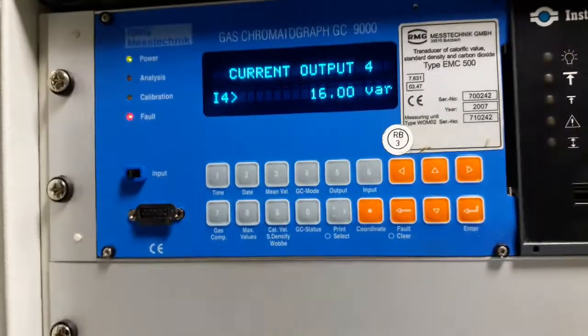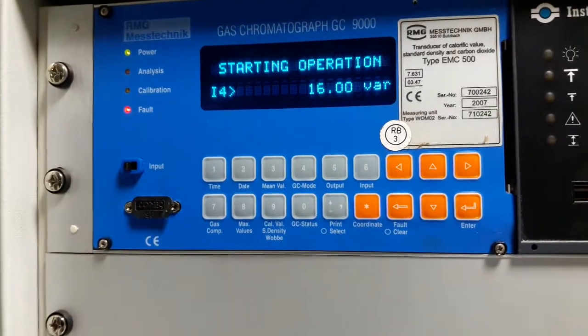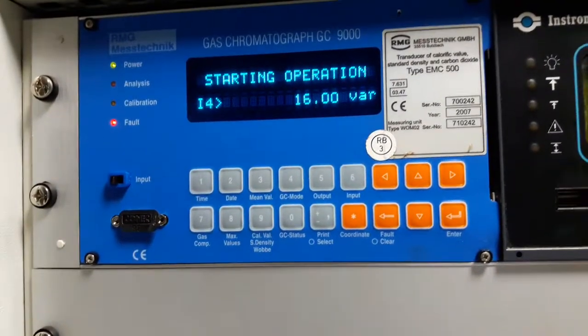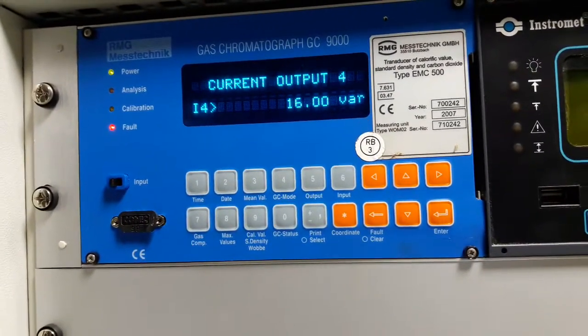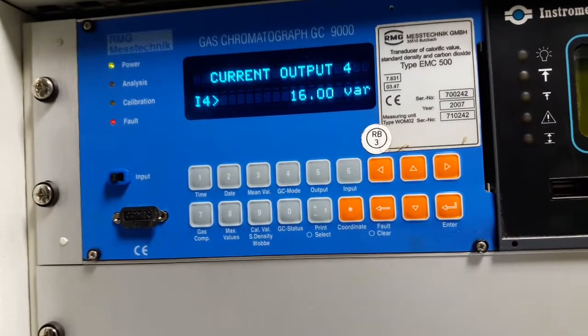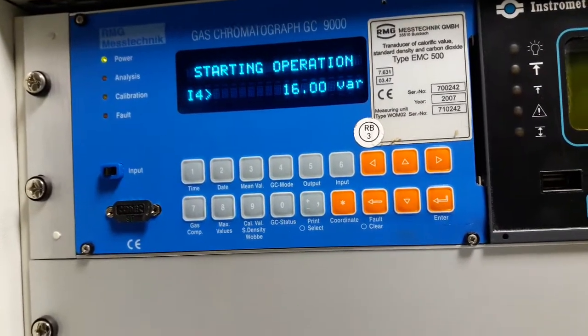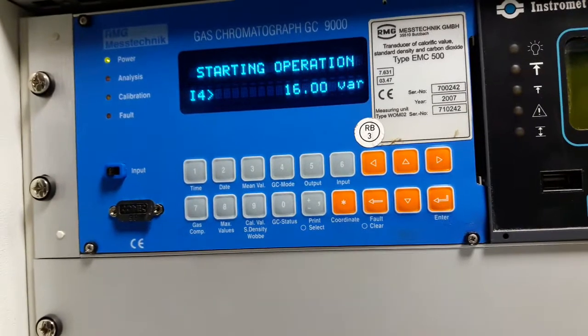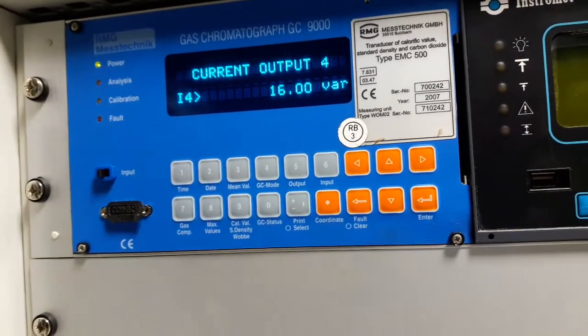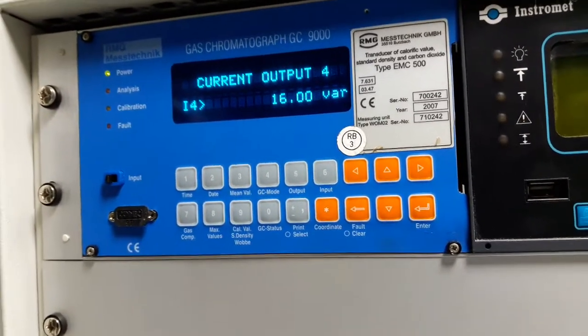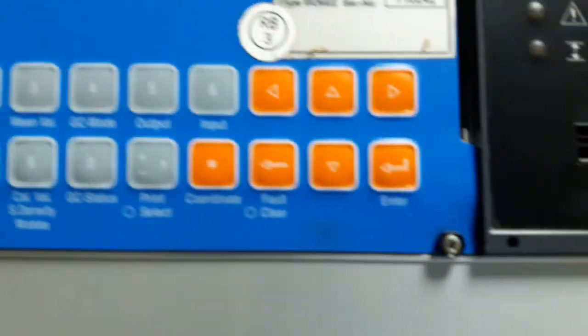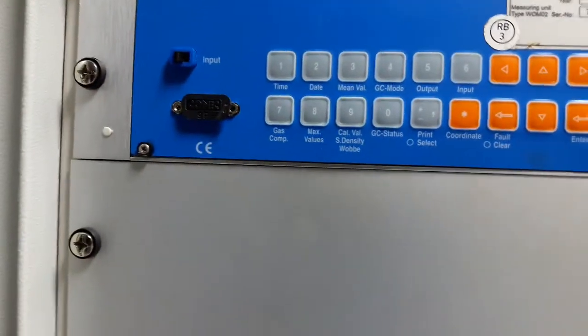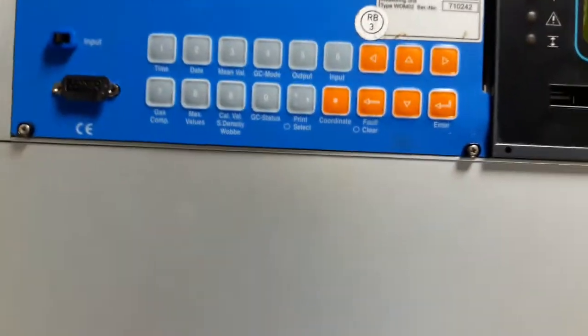This gas chromatograph GC 9000 model, we set it to measure superior calorific value, Wobbe index, and inferior calorific value, standard density, relative density, temperature at base condition, and temperature at condition of superior calorific value. So before starting the unit, if you want to calibrate it, you have to set your calibration cylinder parameter values here.